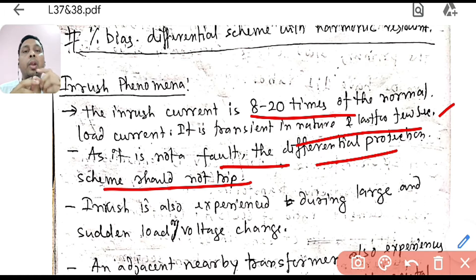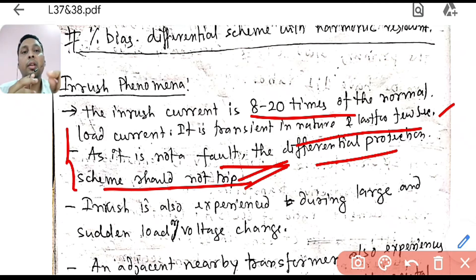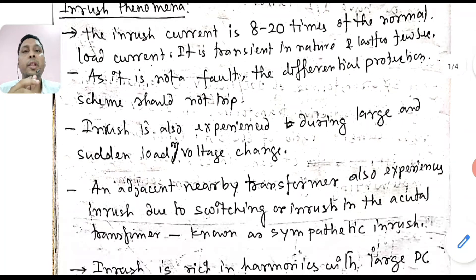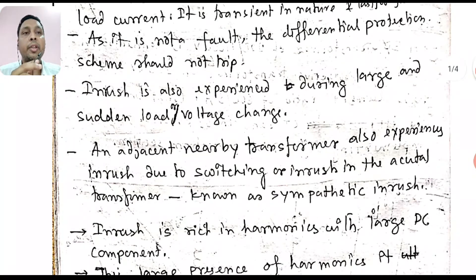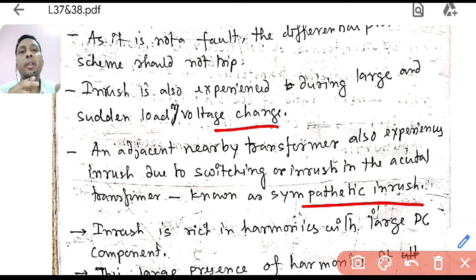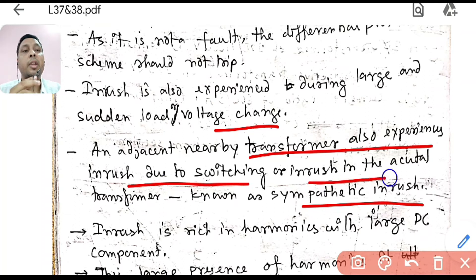Because the inrush current is more than normal load current, there will always be a difference, and that difference will cause the differential protection to trip — but we want it not to trip during this inrush phenomena. Inrush is also experienced during large and sudden load or voltage changes. There is also sympathetic inrush: if inrush occurs in one transformer, the adjacent nearby transformer can also experience the same inrush phenomena.